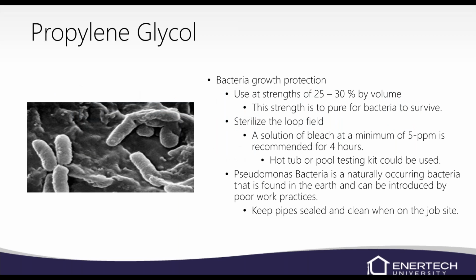Here is that propylene glycol bacteria issue we talked about. Anything of 25 to 30% is too strong for the bacteria to survive. If you do happen to get the bacteria in the system, and what that bacteria is, if you've ever seen the clear slime on fittings or in the pipe itself, that's the bacteria itself. And it gets in the system by any kind of dirt or anything when you're installing the system. And then it'll just feed on the sugar in the glycol and spread throughout the system.